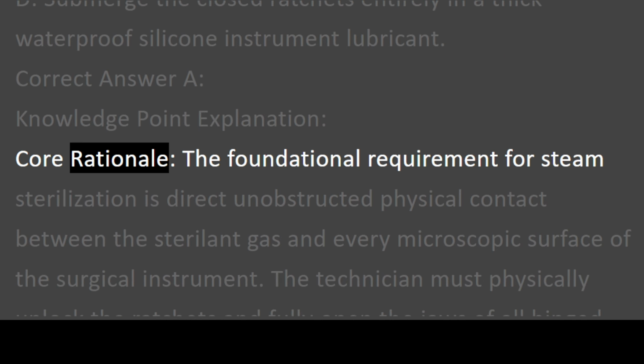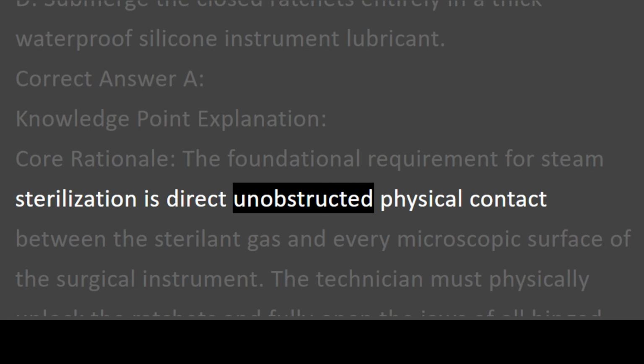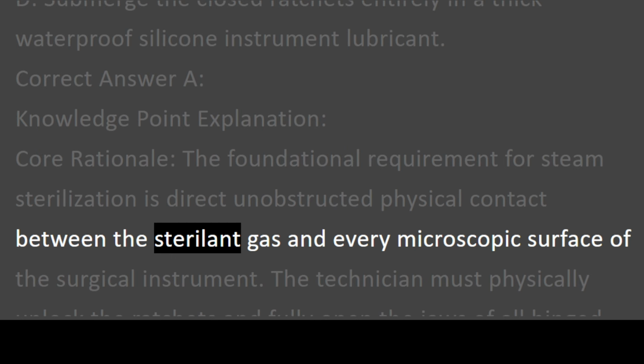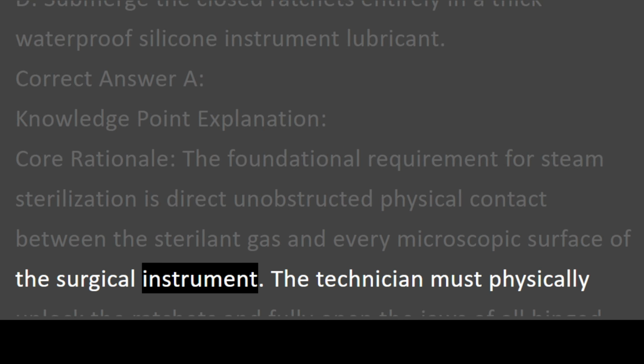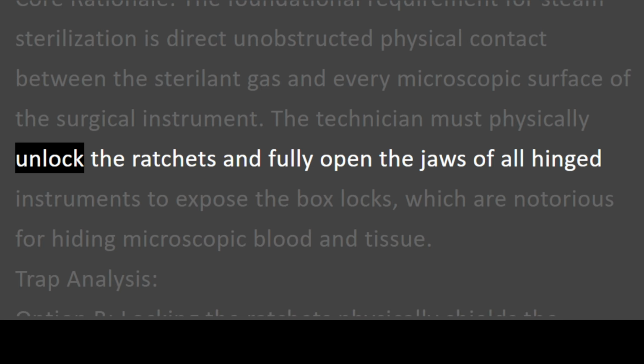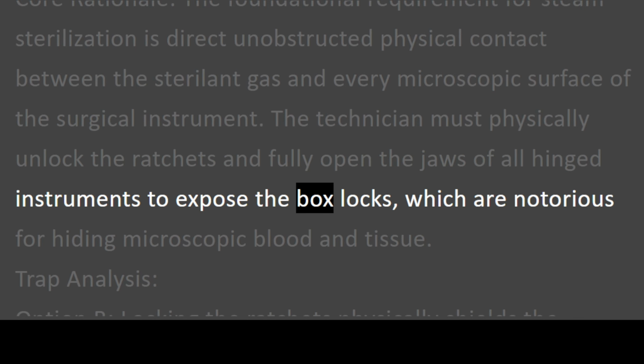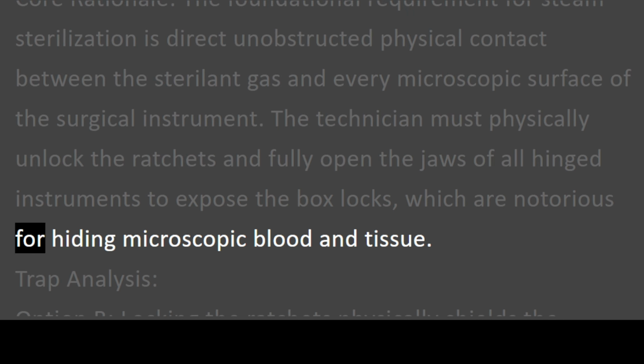Core rationale. The foundational requirement for steam sterilization is direct unobstructed physical contact between the sterilant gas and every microscopic surface of the surgical instrument. The technician must physically unlock the ratchets and fully open the jaws of all hinged instruments to expose the box locks, which are notorious for hiding microscopic blood and tissue.